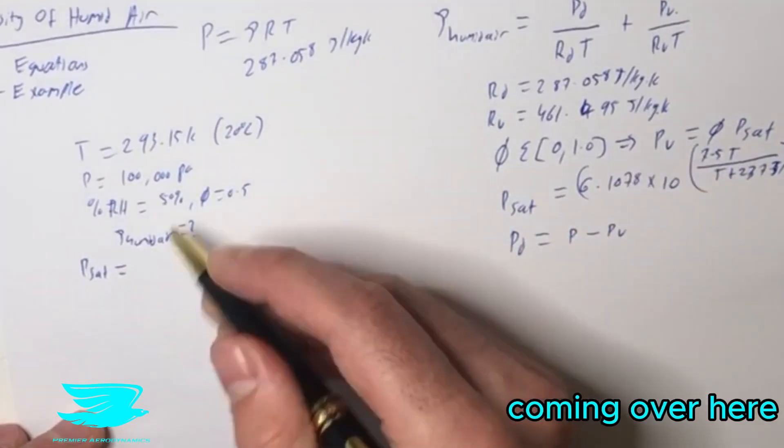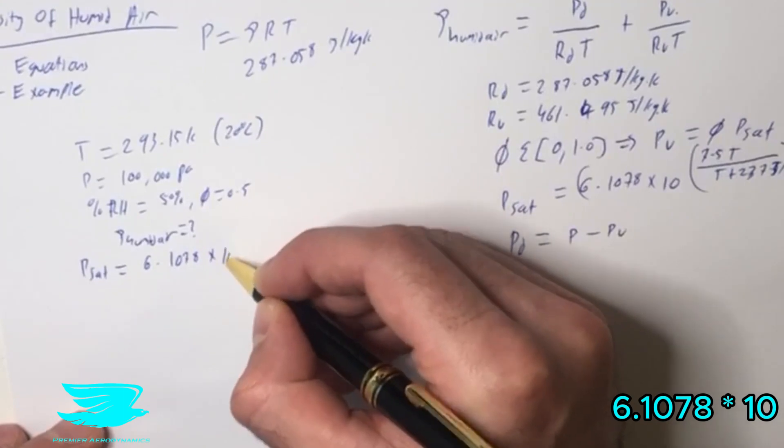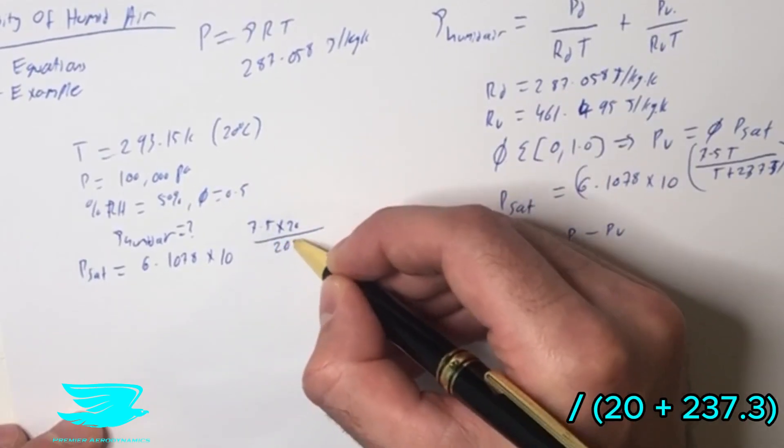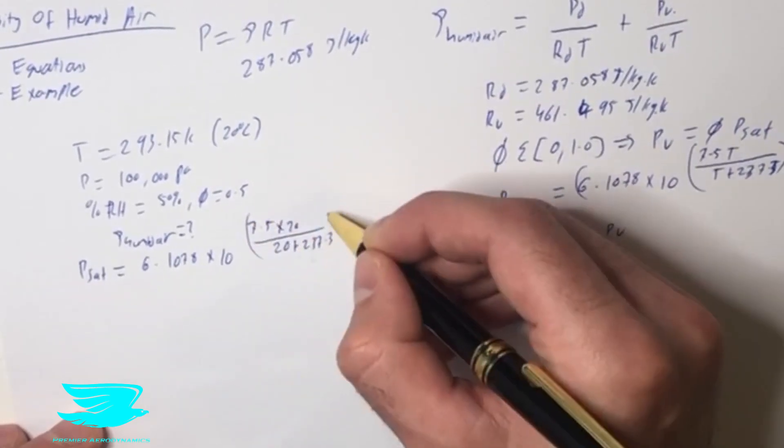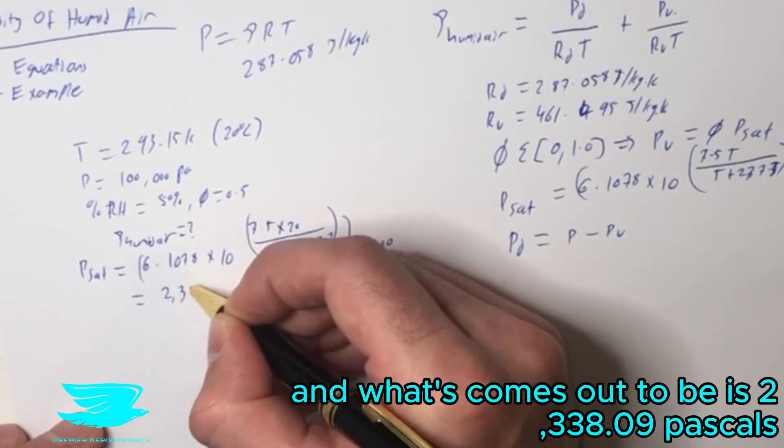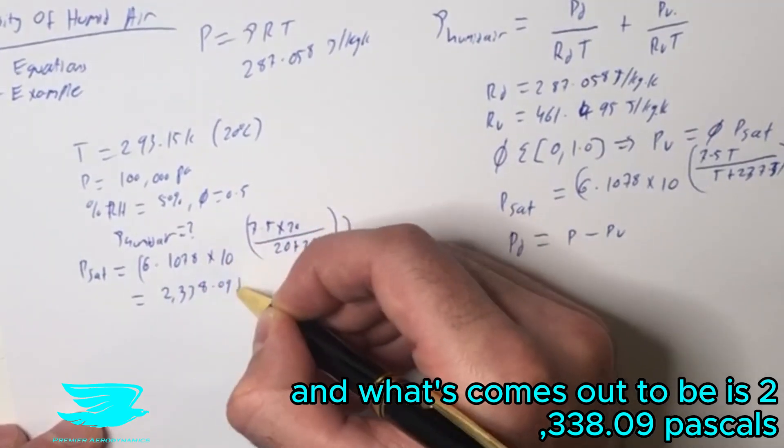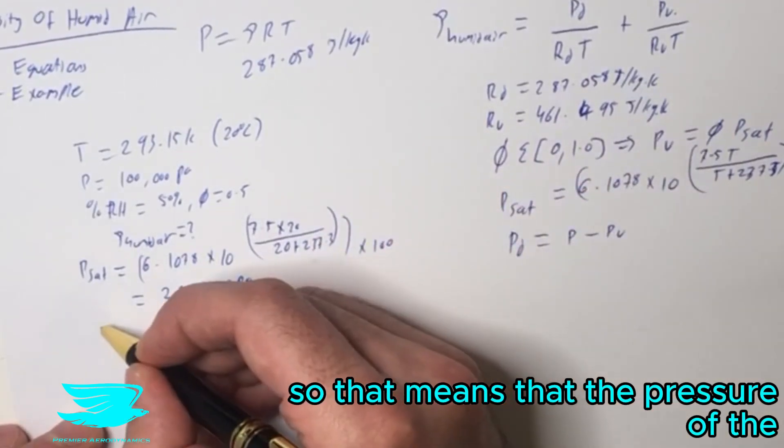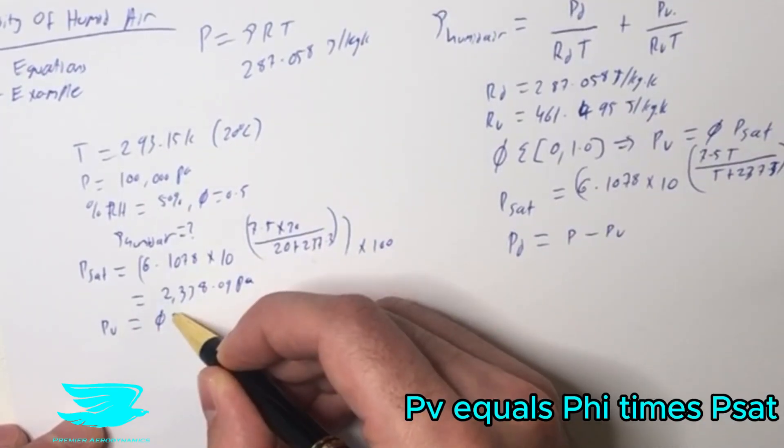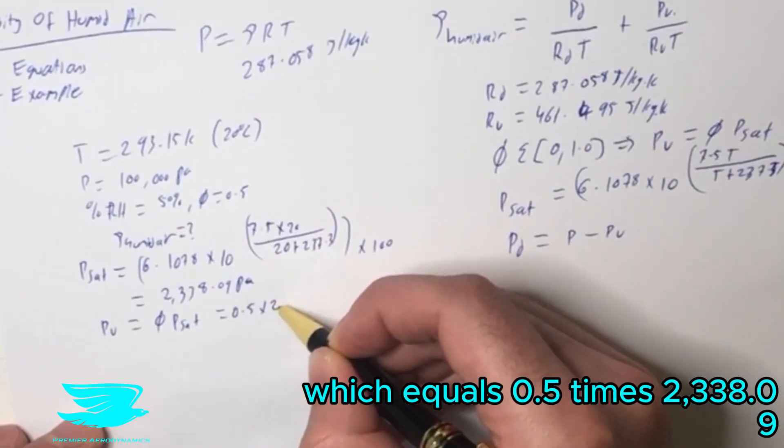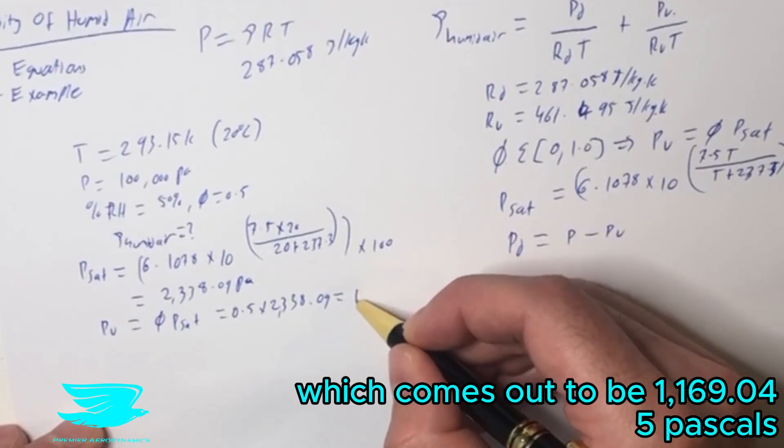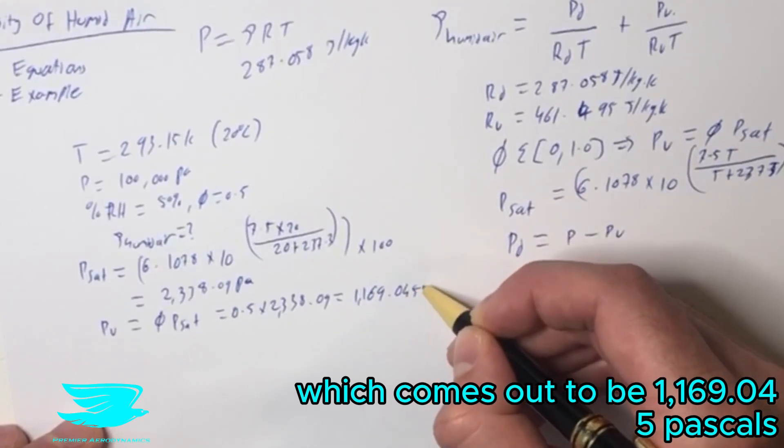PSAT equals, using this equation, 6.1078 times 10. It's 7.5 times the temperature in Celsius, which is 20, divided by 20 plus 237.3. Now times this by 100 in total. What this comes out to be is 2338.09 Pascals. That means the pressure of the water vapor section is PV equals phi times PSAT, which equals 0.5 times 2338.09, which comes out to be 1169.045 Pascals.